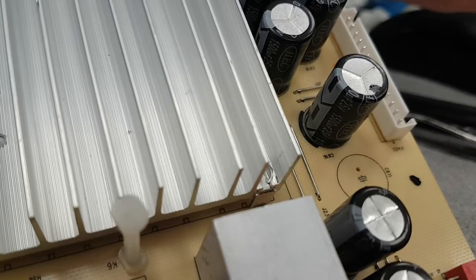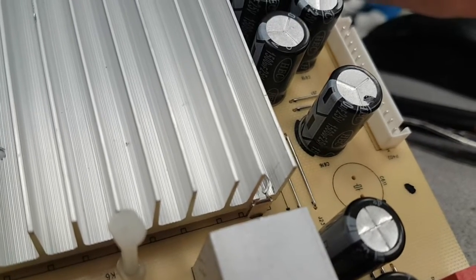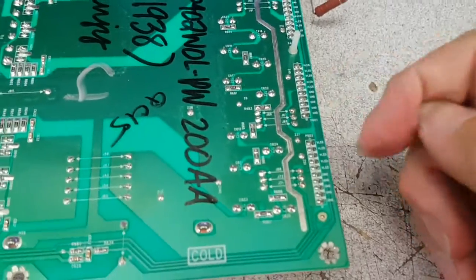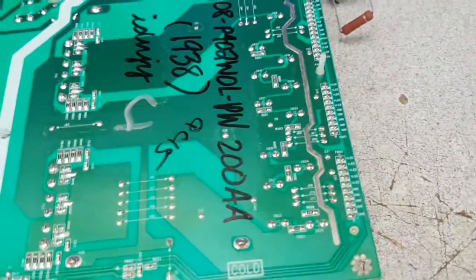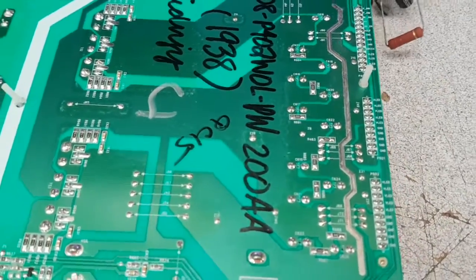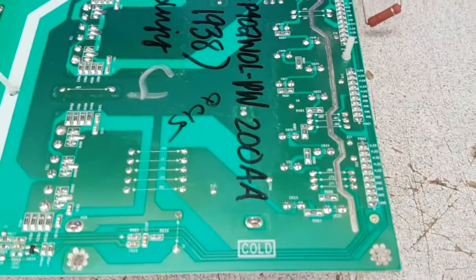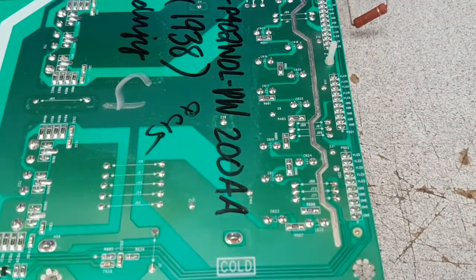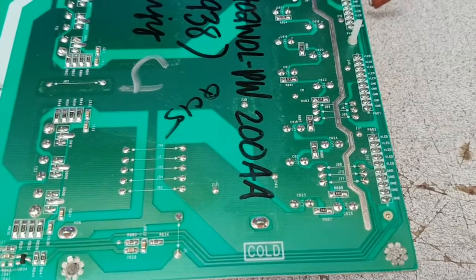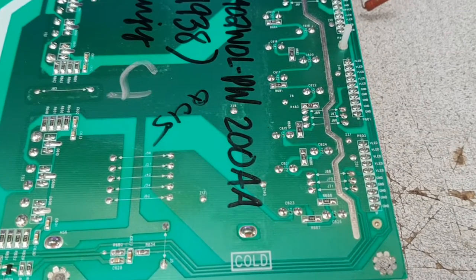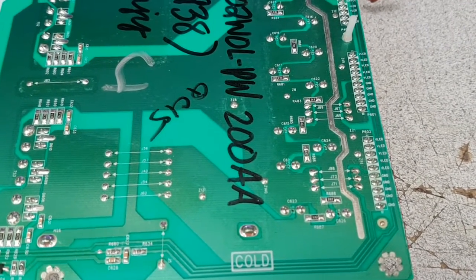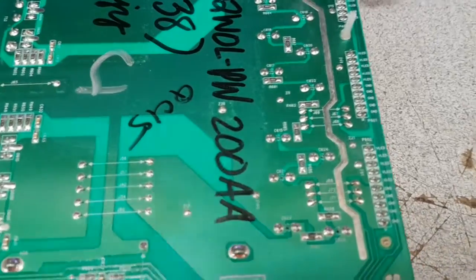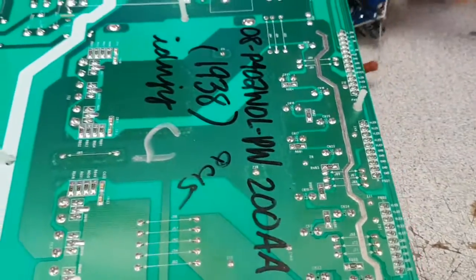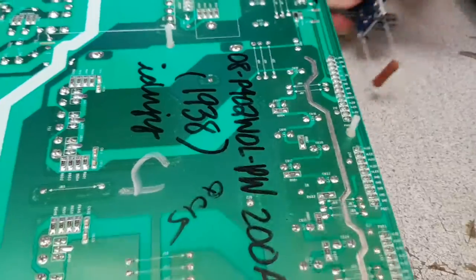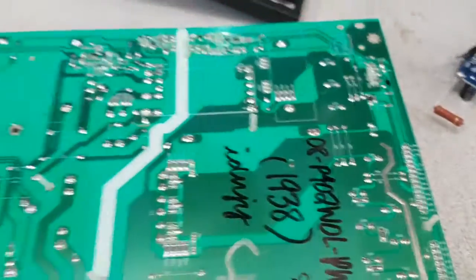You see that they are 1500 microfarads at 25 volts. So that means the highest voltage coming out here could possibly be 24, but it shouldn't be 24, it should be less, because otherwise the capacitor should be rated 35 volts. If they are rated 25 and the board is properly designed, I'd expect the output voltage here is 12 volts. So how to test it, I'm going to get back to this connector in a second.